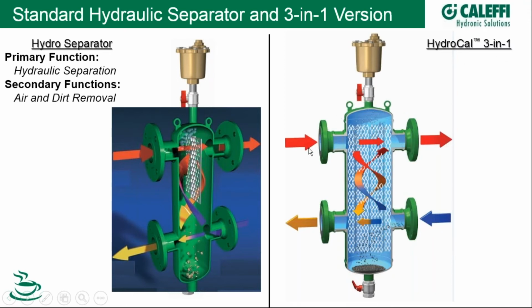On the top, we have taken the baffle and replaced it with a specially designed stainless steel mesh, top to bottom. In the top portion up here, we have dedicated coalescing air separation, high efficiency air separation as you would get from a dedicated air separator. Down here, we have dedicated high efficiency dirt separation as a dedicated dirt separator would do, and also hydraulic separation, so we're decoupling our pumps. Its primary function is actually all 3: hydraulic, air, and dirt separation, all in one.